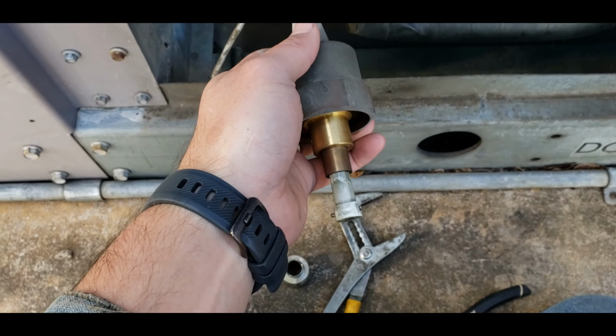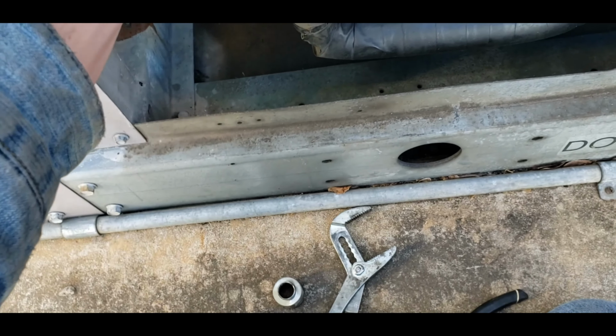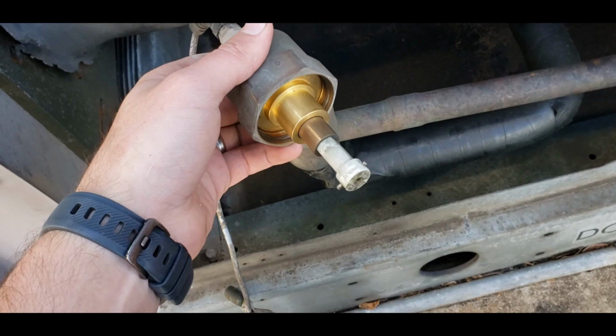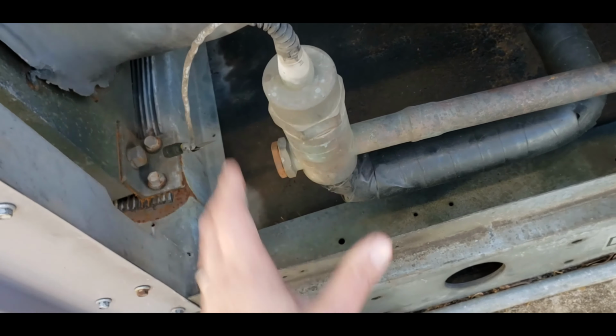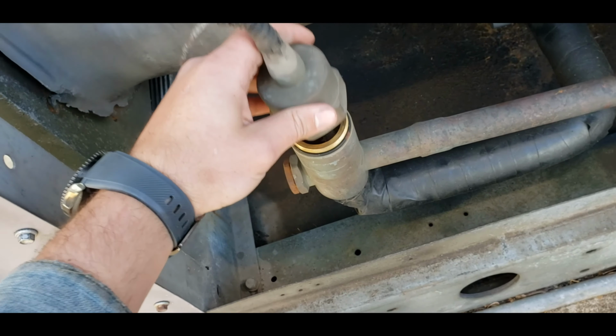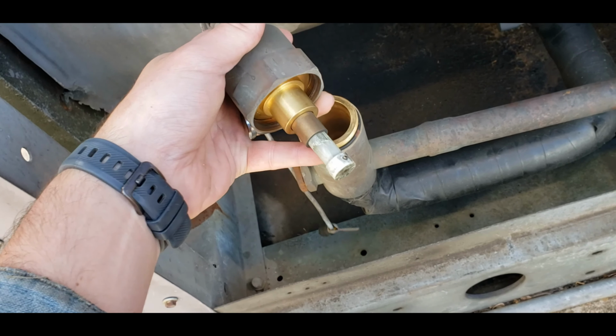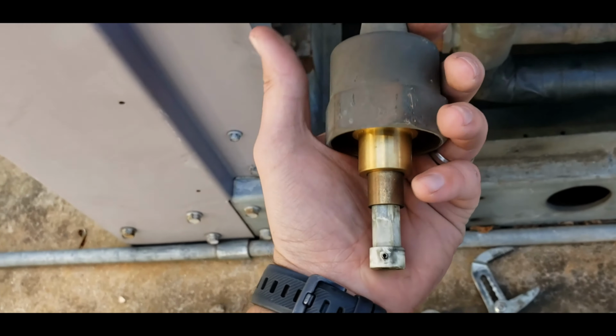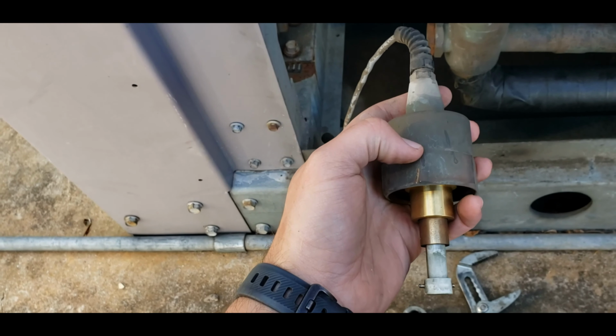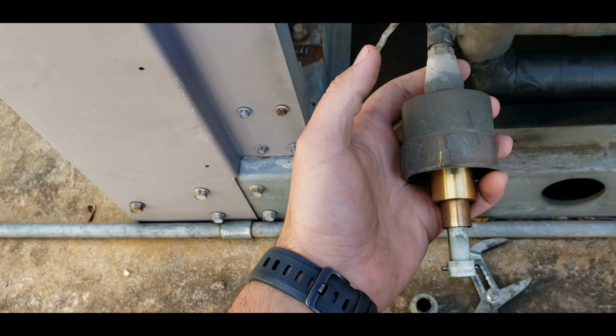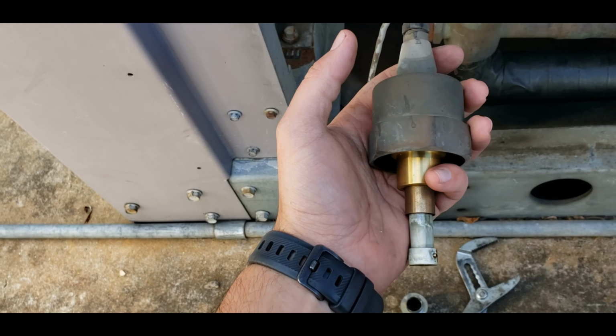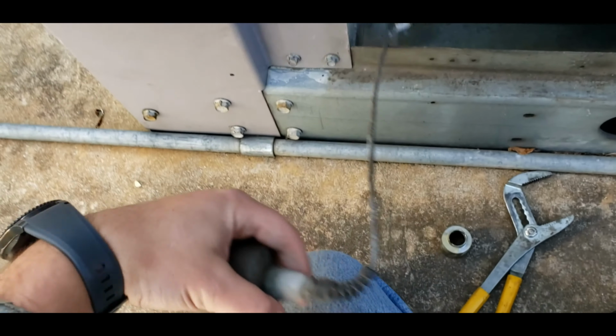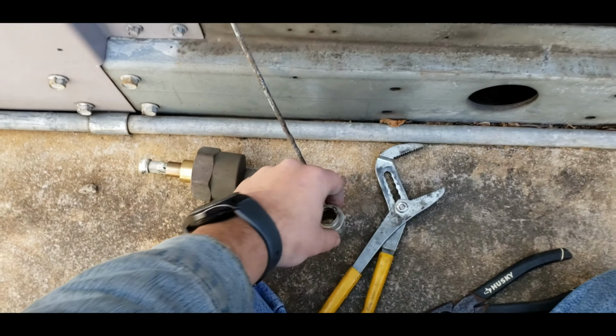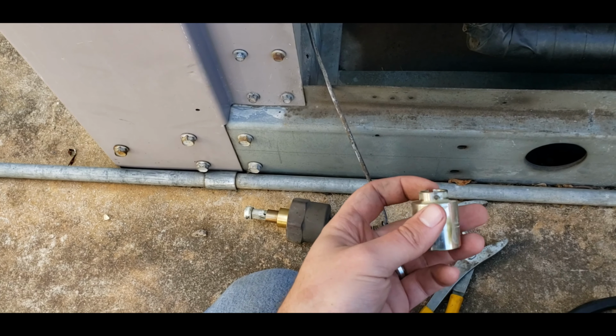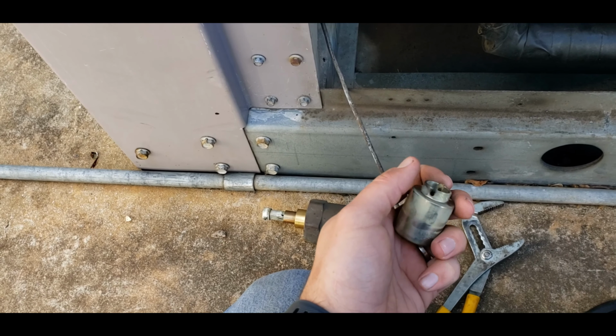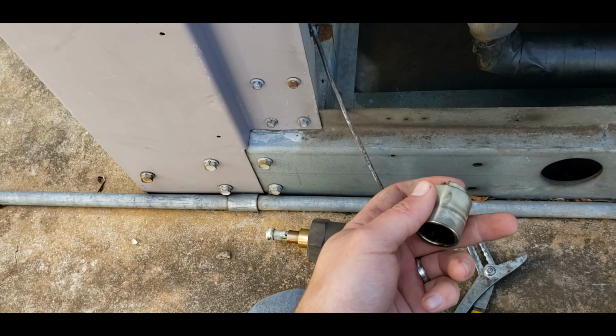Normally, if you were questioning whether this was any good, you'd have to recover the whole system down, but you could pull this out, inspect it, and actuate it. When I was testing it, I could still hear the motor actuating in and out, but it wasn't actually changing anything, and my evaporator kept pumping down on me. So I was trying to figure that out, and at first I thought I had oil in my barrel.